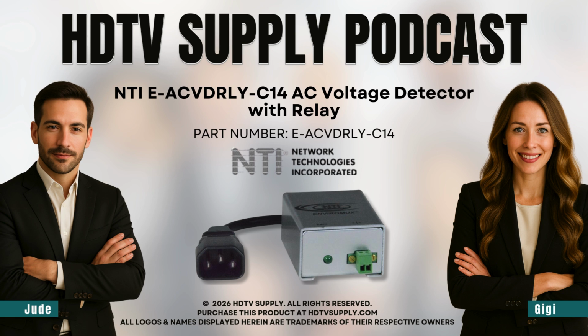Yep. An actionable alert. Okay, so let's end with a final thought for you to consider, going back to that hysteresis gap we talked about. The 55-volt opening, yeah. So we know it registers a power loss when the voltage drops to 55 VAC. But in some of the technical specs, it notes the closing voltage, the point where it declares power as normal again, can be as high as 90 VAC. Right. So the question is, why such a big difference? If it's designed to detect a problem at 55 volts, why does it wait for the power to get all the way back up to a stable 90 volts before it gives the all clear? Think about why the engineers would design it to be so quick to raise an alarm, but so cautious, so slow to say that everything is okay again.